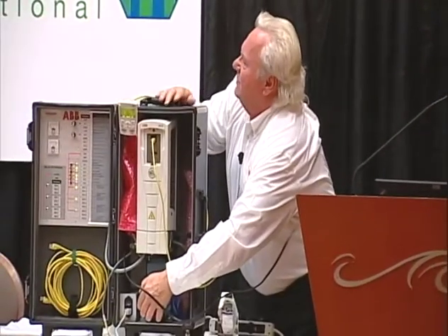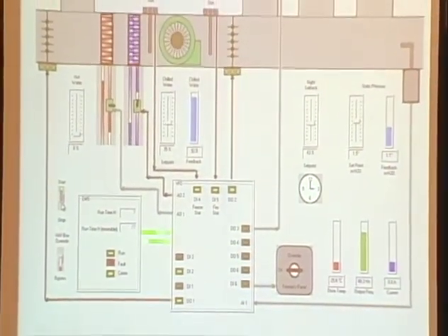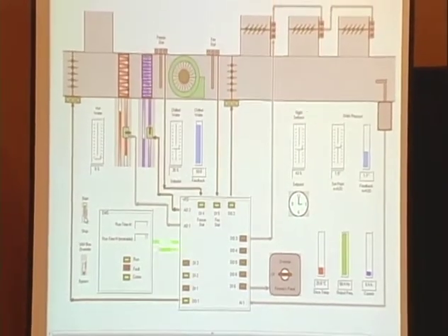So very powerful stuff. As you see, in this case, I'm monitoring temperature, frequency, and current to the VFD. As I mentioned, in my case, there's 73 points or objects of information available, including things I'm not showing here like kilowatts. Didn't make much sense because this little 1/8 horsepower motor doesn't really have kilowatts. I can make it have some amps here by holding on to this motor as long as I can. You see the amps go up in the corner. So 2.5.